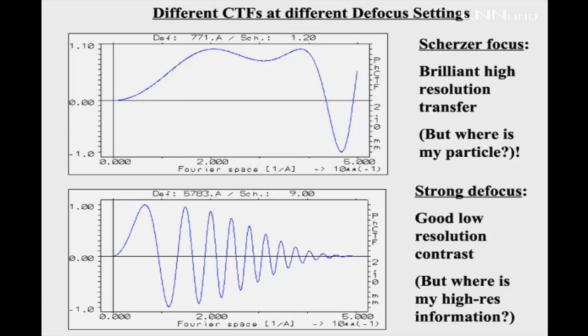This is a lot of theory, but the question is, if you have a transfer function like this or like this, what does that actually do to your image? Your image consists of low frequency details here, a little bit higher, higher. But when you have a contrast reversal of this nature, it actually means that black becomes white and white becomes black. This is one of the most important parameters. You need to make sure that all the data that you're collecting has the same phase. If the phases are flipped over, the information will average out. So knowledge of the CTF is very fundamental, and that is throughout all sciences that use the electron microscope as an imaging instrument.